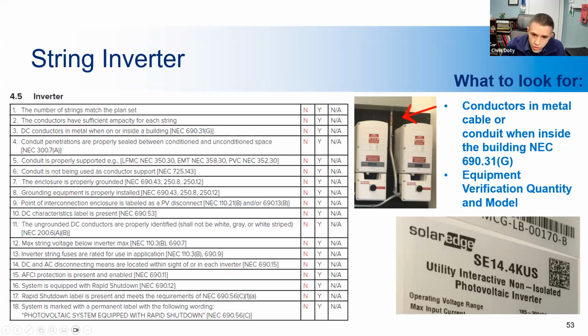So now we're going to talk about string inverters. This section of the checklist asks for equipment verification. It is vital to ensure that the actual installation matches the design submitted in the permit package construction documents. You want to make sure that the conductor sizing is based on the information provided by the manufacturer, and if a contractor substitutes the inverter model, it can be oversized for the conductors carrying the output current. And this is verified by looking at the inverter nameplate, which is typically on the side or underneath the inverter itself.